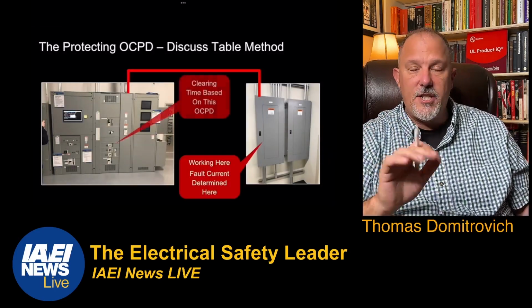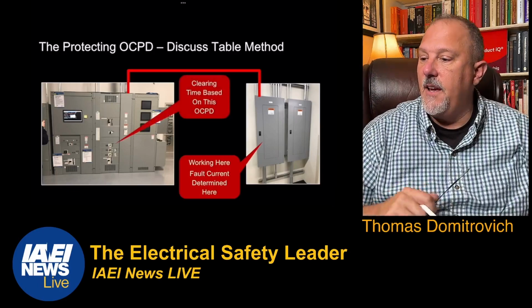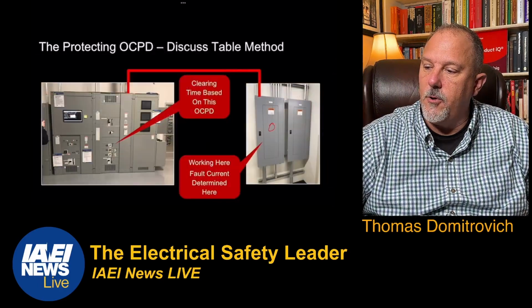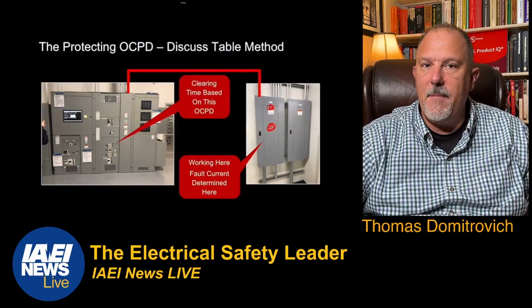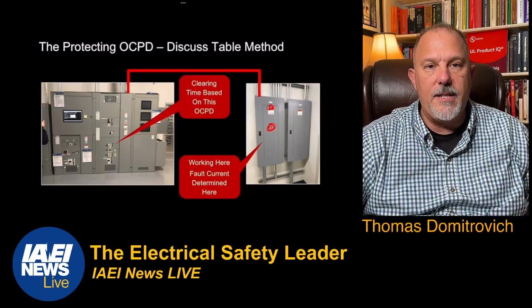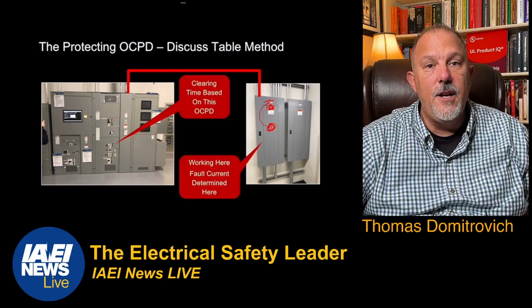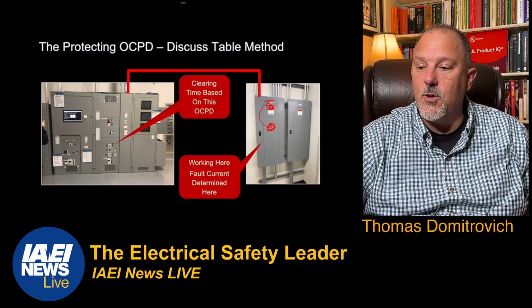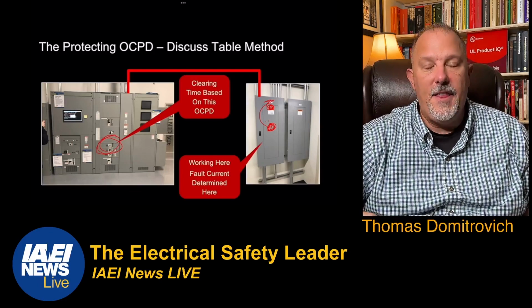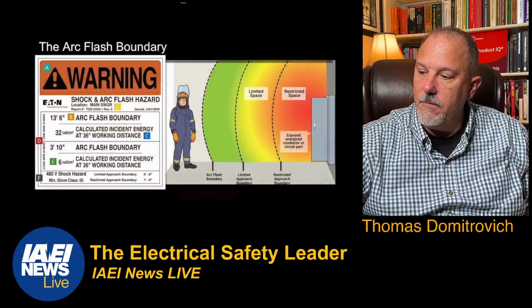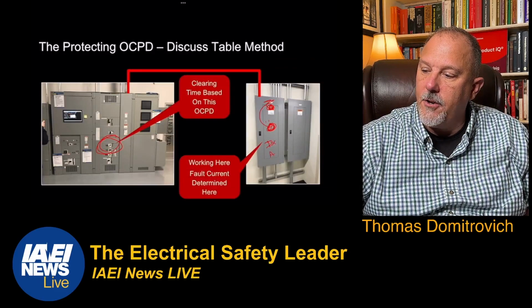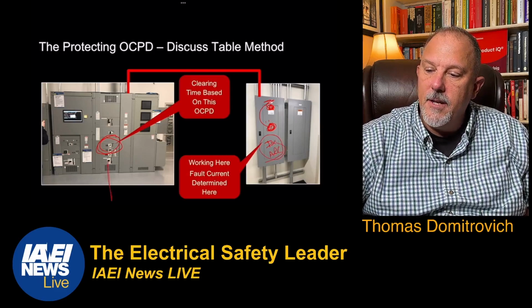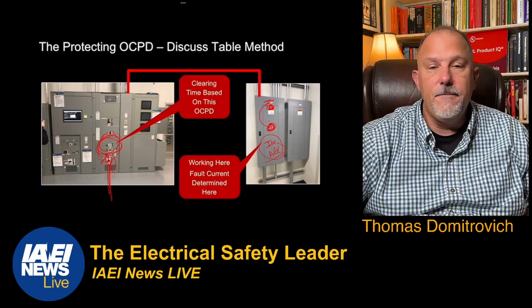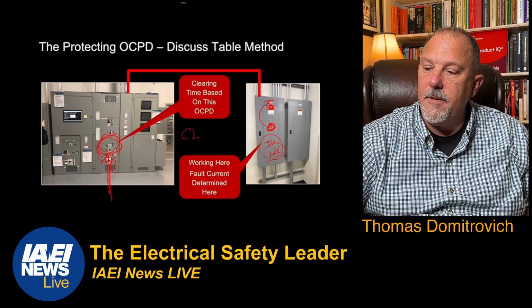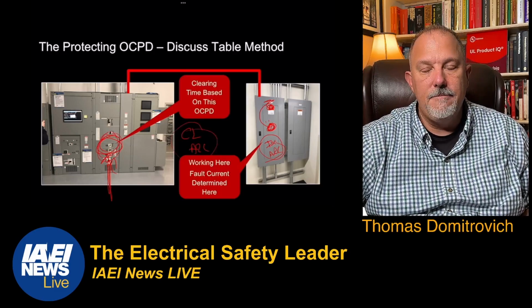Now, the protecting overcurrent device, I've mentioned that term a few times so far. What do we mean by that? If I am performing work in this panel board right here, and if there is a main in here, that main is not what determines the amount of energy that will be released if I'm doing justified energized work in this panel. Because I have to assume line side propagation, or if I accidentally touch the line side lugs of this panel board. The actual clearing time is going to come from an upstream breaker that is feeding that panel board. So I'd have to know what my fault current is here, know what my short circuit and my arcing currents are here, determine the clearing time based upon the overcurrent device that's upstream over there. And that will give me my clearing time and my arcing current, and I can calculate my incident energy.